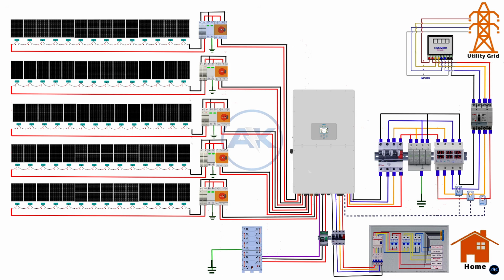For a 3-phase system, use a 3-phase CT set or individual CTs for each phase, depending on the meter type. Each CT must be installed on one phase conductor only. Never place a CT around neutral or around multiple cables together. Open the CT clamp and place it around phase L1. Make sure the arrow or marking on the CT is pointing toward the grid, not toward the load. Correct direction is critical. If the CT is installed backward, the inverter will not control export correctly.